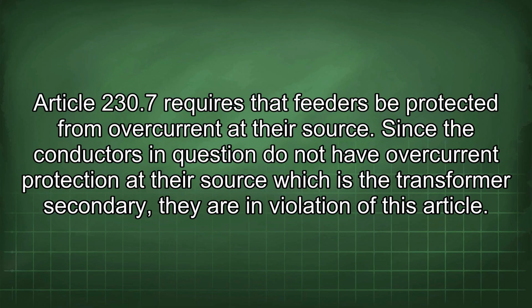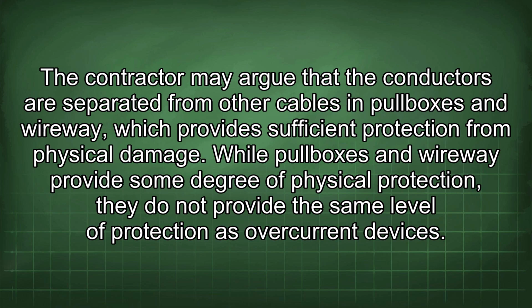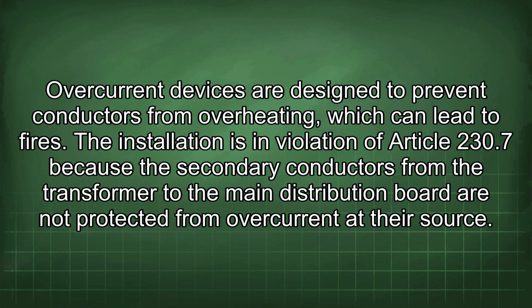Since the conductors in question do not have overcurrent protection at their source, which is the transformer secondary, they are in violation of this article. The contractor may argue that the conductors are separated from other cables in pullboxes and wireway, which provides sufficient protection from physical damage. While pullboxes and wireway provide some degree of physical protection, they do not provide the same level of protection as overcurrent devices. Overcurrent devices are designed to prevent conductors from overheating, which can lead to fires.